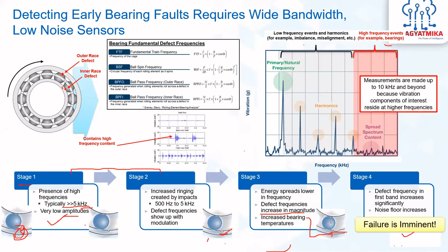If we have only very small measurement ranges, we will not be able to detect more of the predictive conditions. But if we have the displacements and wider frequency ranges, we are able to detect those things, and we will be able to predict and analyze better. So, wider bandwidth and lower noise. Even if the amplitude is very low, we are able to detect that this is the initial stage of wear, which you can see over here: we have the higher frequencies, but the amplitude is very low. This was the initial stage of the defect, and we can do the maintenance better. Whenever we are implementing CBM solutions on our machines, these four parameters are very necessary.